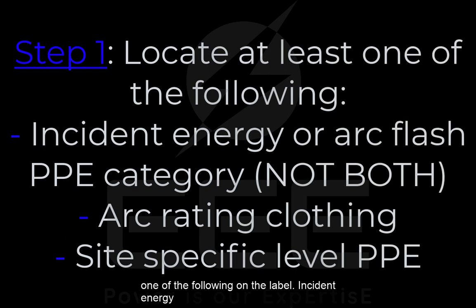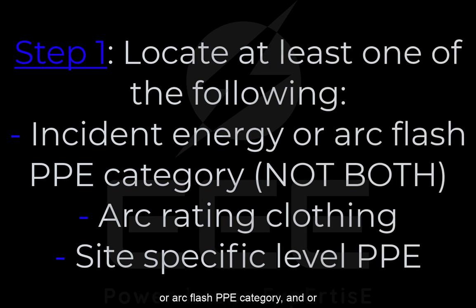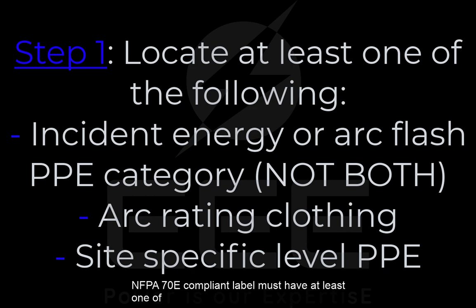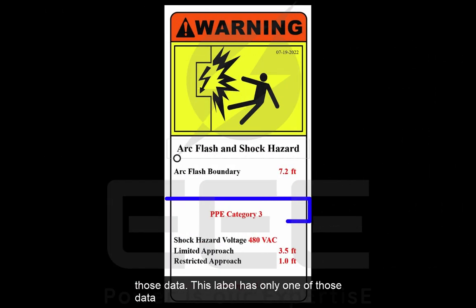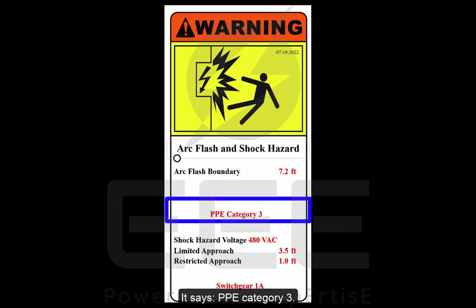Step 1. Locate at least one of the following on the label: incident energy and/or arc flash PPE category and/or arc rating of clothing and/or site-specific level of PPE. Any NFPA 70E compliant label must have at least one of those data. This label has only one of those data. It says PPE Category 3.